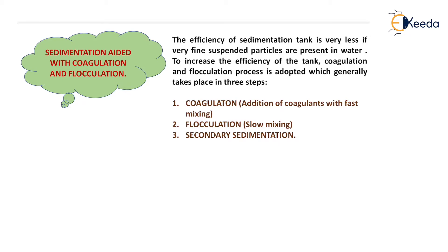To remove that type of particle we generally need certain chemicals known as coagulants, due to which they will grow in size, and after growing in size they will settle down because of their self weight. That type of process is known as sedimentation aided with coagulation and flocculation. The efficiency of the sedimentation tank is very less if very fine suspended particles are present in water. To increase the efficiency of the tank, coagulation and flocculation process is adopted which generally takes place in three steps.